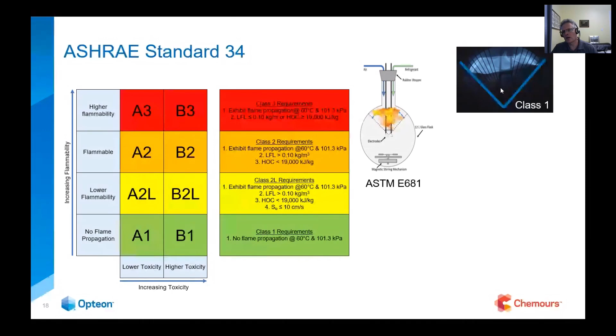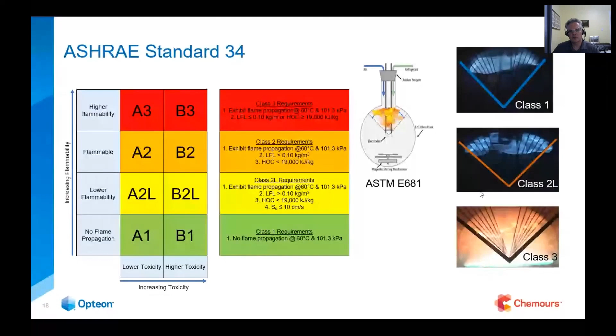Here's a class 2L, and it just falls outside of that 90 degrees, so it ends up being a flammable class. But I'm going to show you a hydrocarbon, a propane or an isobutane. It's very different, and this is what it does. It basically fills the vessel as it combusts in here, and you can see that although the 2Ls are combustible, they are very similar to class 1s, but nonetheless, due to the testing method, they fall into the flammability category.